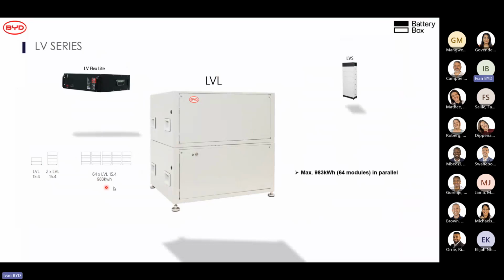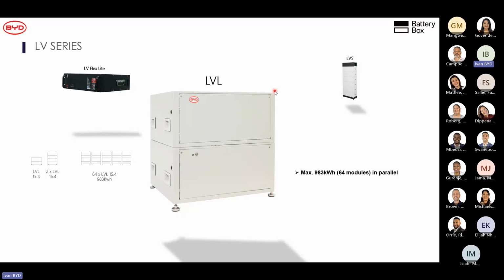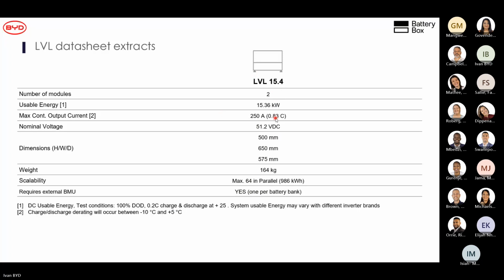There is actually a system installed in Johannesburg that's got 64 LVLs on one site. It's a Victron system. I do believe it's 12 15 kVA Victron Quattros. So there is actually a system that is installed at that size, and it's worked perfectly since the day it was installed. You can see it's a 0.8 C battery with maximum output current of 250 amps. And you do need 1 BMU per battery bank.